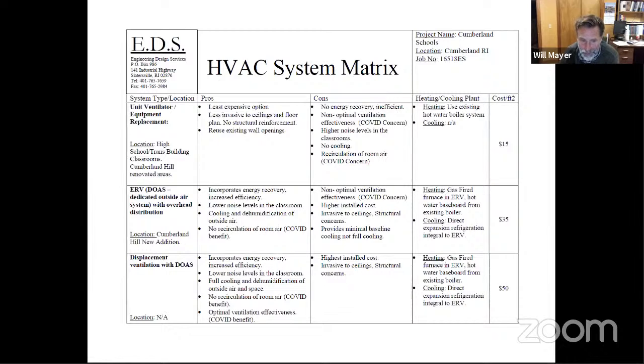There are other benefits to them. One is the addition of cooling, which obviously will increase your operating cost. It just comes down to what's important. Cooling hasn't really been identified in these areas as something that's 100% necessary, but the energy recovery does provide about a 60% savings in outside air treatment costs, which usually translates to about 30% overall heating cost savings.